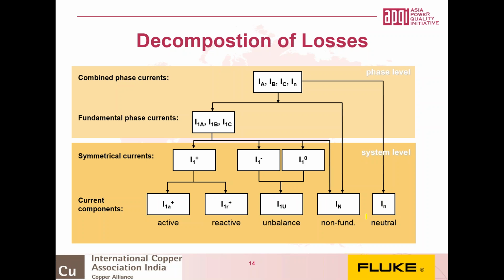The loss due to the reactive current can be reduced by compensation, by reducing the phase shift between fundamental voltage and current using compensation capacitors. The loss due to non-fundamental currents can be reduced either by avoiding generating harmonics, or by using passive or active filtering, or a combination of both. And the loss due to unbalanced current can be reduced by balancing the system or compensating. And the loss due to neutral current can be reduced by not generating neutral current in the first place, and as that's usually mostly the result of harmonics or unbalance, if you take those other steps, then the neutral current is going to be low.